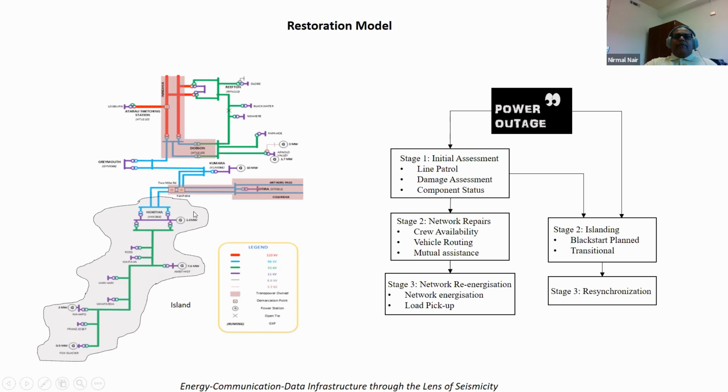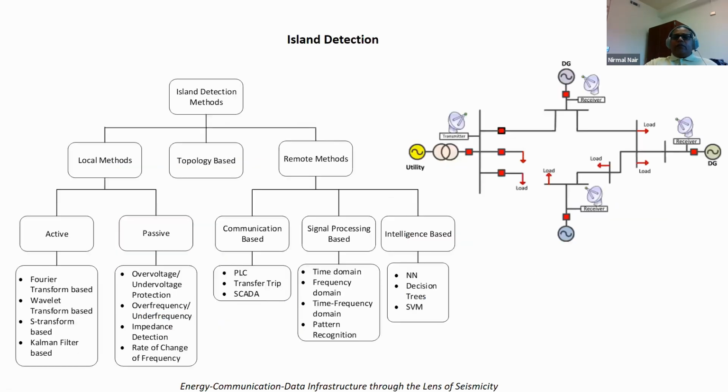local resources here. This was really tested, incidentally, during FEHI in 2018. And this part of the network stayed connected for about 48 hours. So it is possible, if fuel resources are there, that we could extend this idea to a couple of months, for instance, or a few weeks.